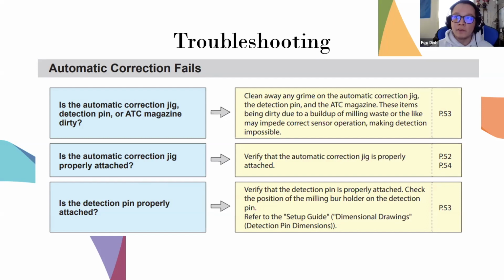Definitely, for sure. On the older Roland mills, it was way worse. You'd have to eat off the mill before it calibrates. It had to be that clean. So it still needs to be that clean now. I'm not saying some zirconia dust where the vacuum is is going to cause a big deal, but where the pin is making all these contacts, it has to be clean, 100%.